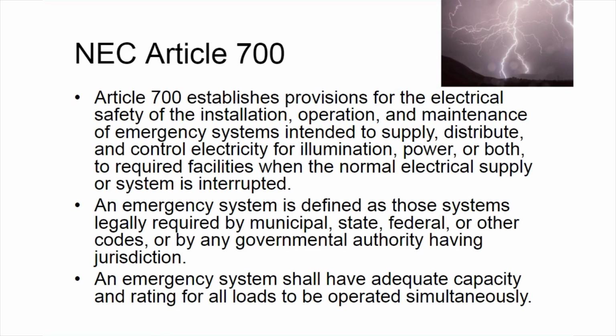So let's take a quick look at Article 700, which is emergency systems. This article established provisions for the electrical safety of the installation, operation, and maintenance of emergency systems intended to supply, distribute, and control electricity for illumination power or both to required facilities when the normal electrical power or system is interrupted, and specifically for illumination essential for safety to life. Safety of life, human life. These are NFPA 110 Level 1 systems and typically are classified Class 1.5, Type 10. So 90 minutes of runtime, start the load on emergency power in 10 seconds or less.